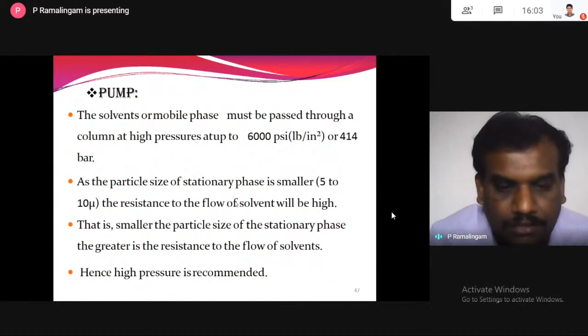Whatever high pressure develops in the column is not only because of the flow of solvent, and not only because of the pump. The high pressure built in the HPLC system is a combination of both the pump and the column particle size. That's why a lower particle size and well packed column, as well as a mechanical pump with a high flow velocity, give a high pressure in your HPLC. This high pressure is converted into high performance.